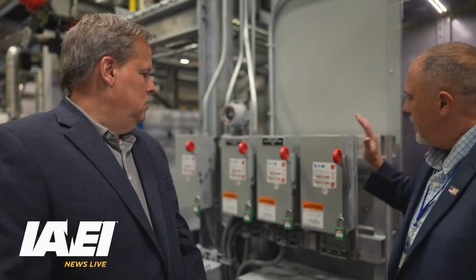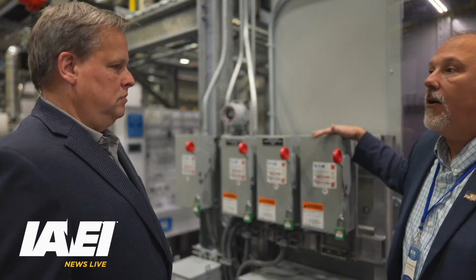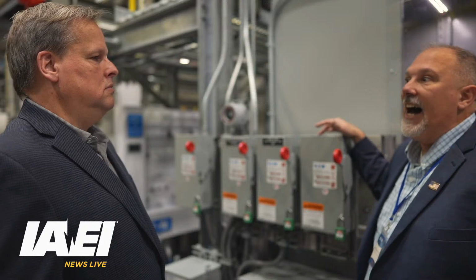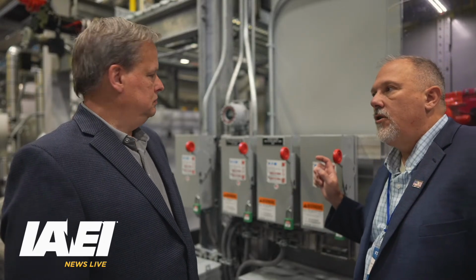All right. Okay, so let's get back to this. It's 11:48. We still have about 10 minutes. We went over that: enclosures, switches, and circuit breakers shall be externally operable. That means like this. This is a fusible disconnect, and it's externally operable. I don't have to open the door. In some cases, with a circuit breaker, I may have a rotary disconnect, even if it's a fusible disconnect. It doesn't have to be a handle this way; it could be rotary as well. There are a lot of different ways to turn things on and off inside. In general, though, you have to have that external operation.